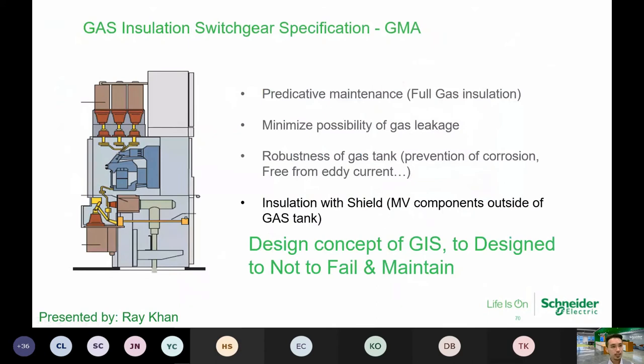Okay, so you can see here is the breakdown of the GMA model. One of the very interesting questions is on the switchgear VTs. The VT is actually located at the bottom. You can see there's a shaft that goes in, so they actually have contact. The indication here is just to show how easy it is to disconnect the VTs, the voltage transformers. We also see that in some VT designs, customers prefer to house it outside the panel. But our recommendation is to have it together with the switchgear itself, because when it comes from the factory, it comes together with the switchgear and everything is tested as one.